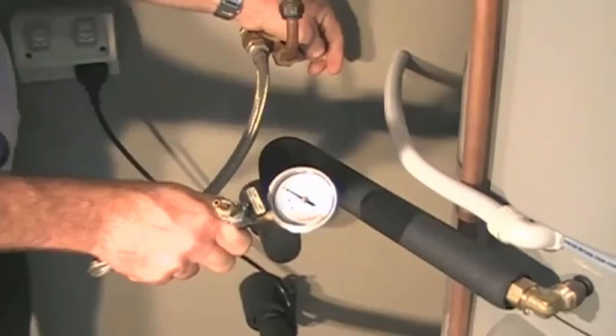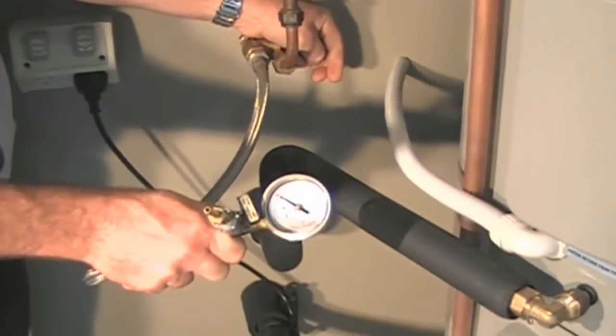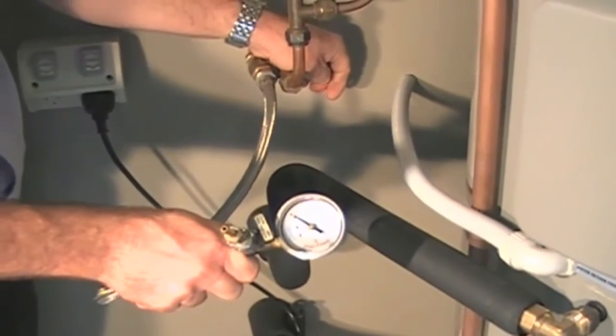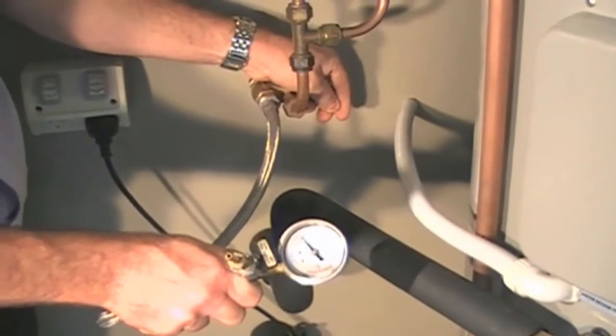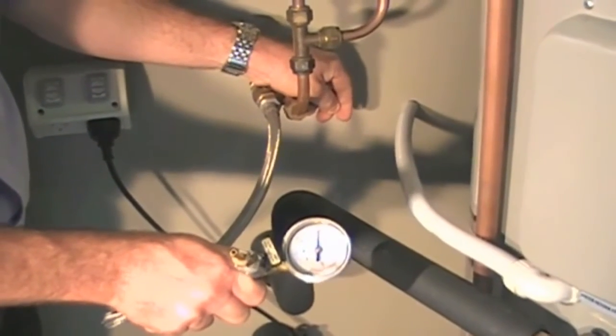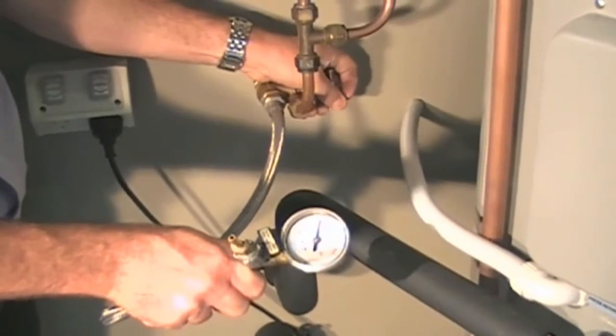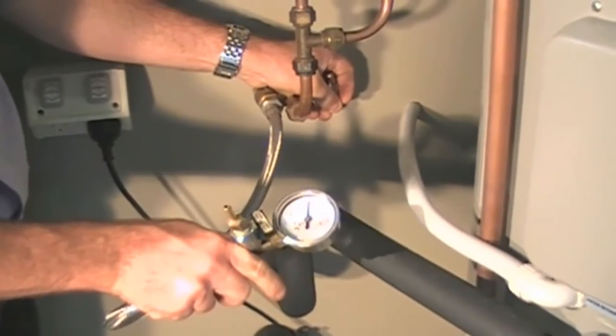Check the mains pressure. If it is over 1100 kPa, connect a pressure limiting valve as required by law. If it is over 800 kPa, consider connecting a limiting valve as this may prevent the possibility of water hammer if it is going to occur.